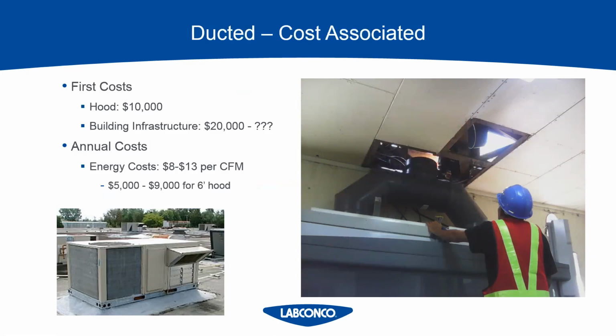And these are the startup costs. One way to lower the number is to use a high-performance hood that doesn't require as much CFM as a typical hood. The high performance hood is a totally different topic in itself. So to keep it simple, I'll just say that the lower the CFM, the lower your upfront bill and the lower your annual bill. So if you can lower your CFM, which is the cubic feet per minute of air that's being exhausted out of the ducted hood. So energy costs are going to vary depending on where you live.